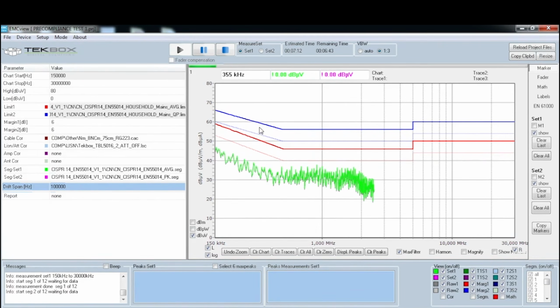As you can see from the screen, we have average scanning results showing here, and currently it is still below the margin line, which is pretty good. The first scan also starts from 150 kilohertz to 2.5 megahertz, and as we just speak, the next segment data will be now put in again.